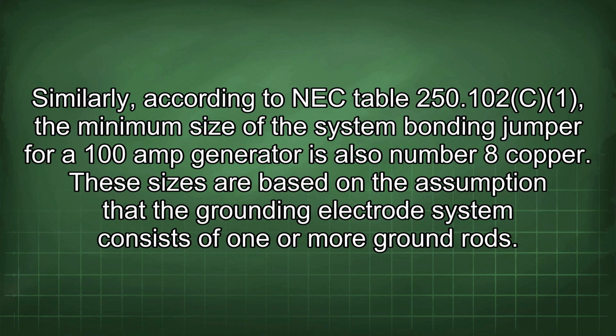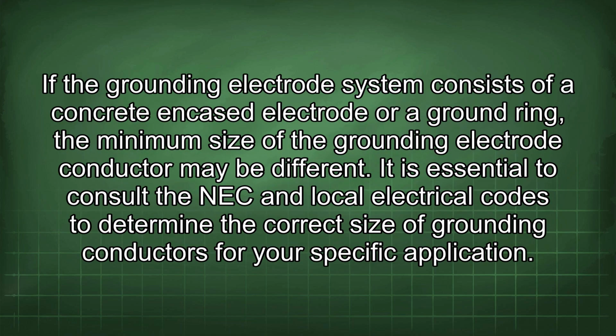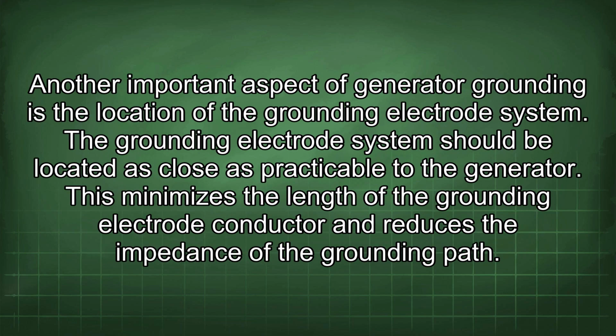These sizes are based on the assumption that the grounding electrode system consists of one or more ground rods. If the grounding electrode system consists of a concrete encased electrode or a ground ring, the minimum size of the grounding electrode conductor may be different. It is essential to consult the NEC and local electrical codes to determine the correct size of grounding conductors for your specific application.